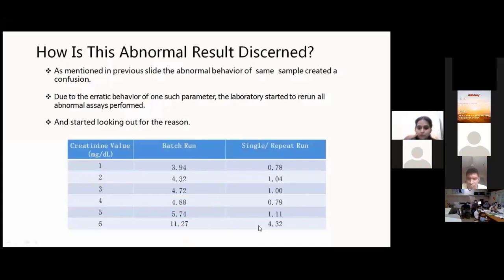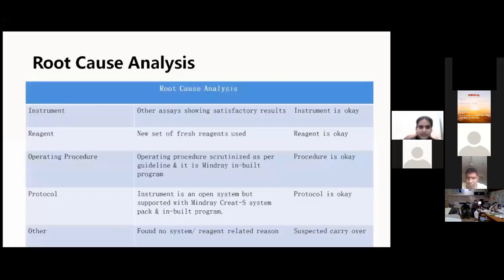A value of 11 was obtained, whereas the actual value was 4. So this was a very scary thing. Root cause analysis was done, and we started looking for all the possible causes. First, we looked at the instrument causes. All the other assays were showing satisfactory results, which meant the instrument was functioning okay. Reagent: we tried with a new fresh set of reagents, so the reagent end was okay. Operating procedures were scrutinized as per the protocols, and we were using the Mindray Creat-S system with an inbuilt program, so the protocol also was okay.